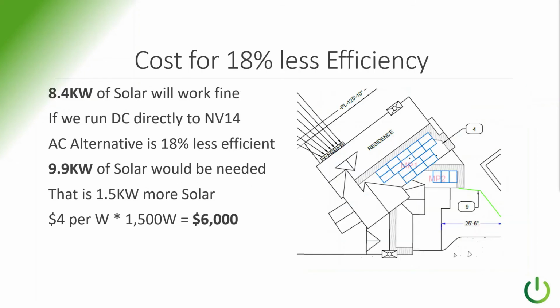That's a lot. So what does 18% efficiency difference look like? You and I were discussing it, we wanted to work up a system. So we first worked it up where this particular system, an 8.4 kilowatt of solar, would work fine if we ran the PV power as DC directly into the NV14. Now, the AC alternative being 18% less efficient, we calculated we would need 9.9 kilowatts of solar panels on the roof. That is 1.5 kilowatt more solar needed for the same efficiency.